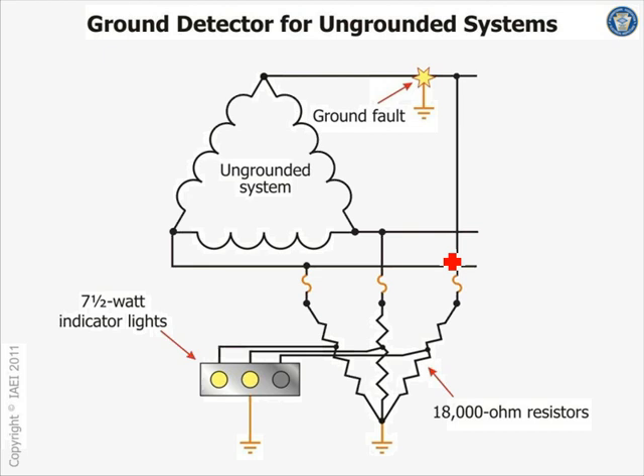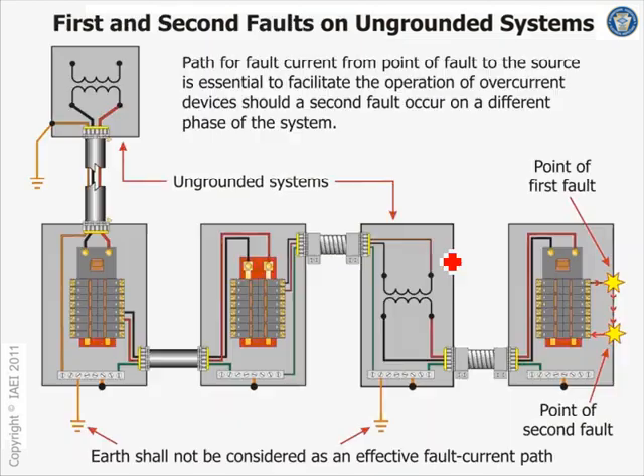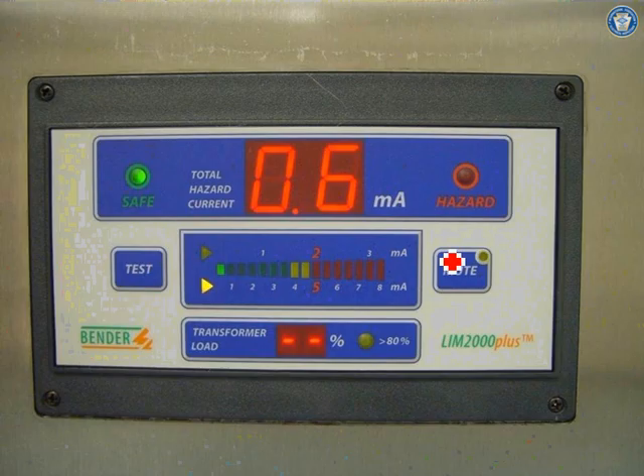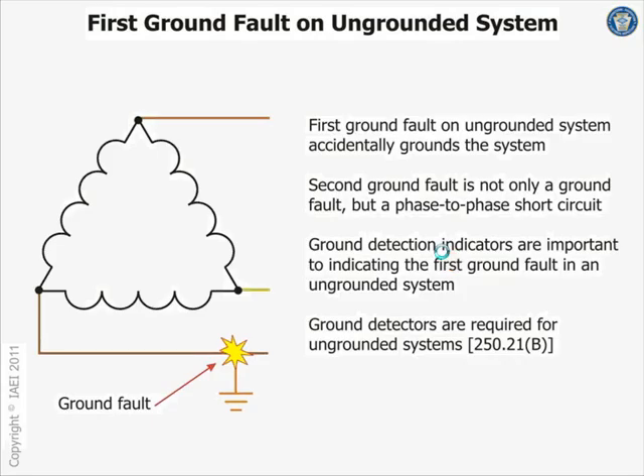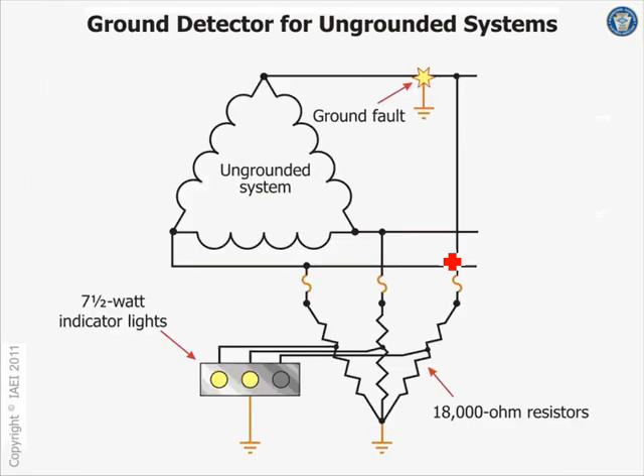If one of them goes off, that's an indication that a ground fault has happened on one phase. That's not sophisticated stuff like what you looked at here, measuring it through sensors. That's just as simple as a couple of lights. If one of them dims or goes off, this means one phase has gone to ground. Your power system will continue to operate properly.